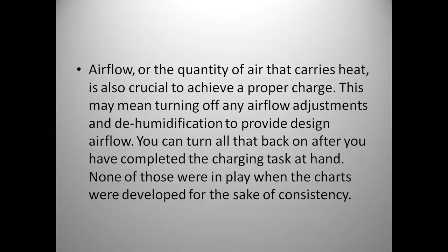Some other factors: airflow, or the quantity of air that carries the heat, is crucial to achieve a proper charge. Not only is the amount of airflow crucial and critical, your static pressure is even more crucial in some cases. If your static pressure is above 1.0, your charge may look good and it may operate okay. It will probably operate fine in cooling, but when you go into heating, that's when everything changes. That's when you'll start getting, in some cases, overcharge, high pressure events. You'll also get a consistent batch of inverter errors, different error codes associated with that. So airflow is super crucial, and so is your static pressure.